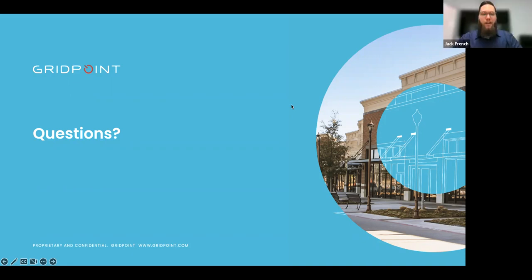That's a really good question, and the answer is no, it's kind of all encompassing. A lot can influence your building's energy demand, and you can achieve demand savings by implementing a lot of different strategies. You can certainly reduce your overall building demand by keeping your set points close to best practice. If your current occupied cooling set point is 72 and you go to 74, you may very well lower your building's demand. You may not, because HVAC runtime is influenced by weather.